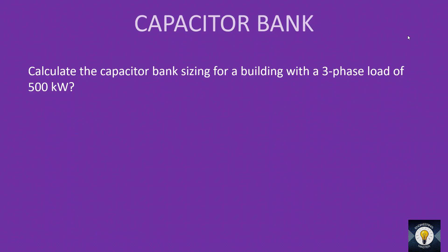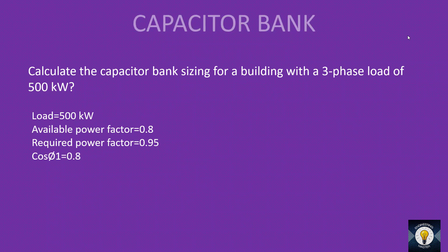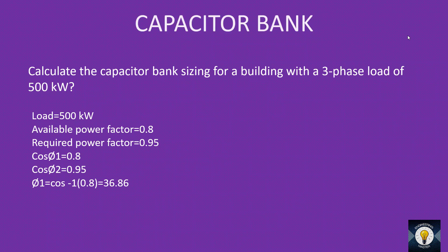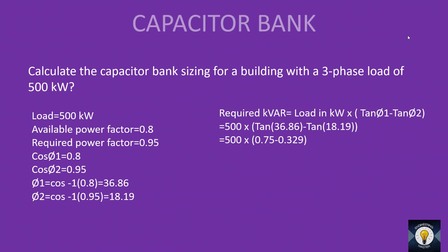Let us solve one more problem. Calculate the capacitor bank sizing for a building with a three-phase load of 500 kilowatt. Available power factor is 0.8, required power factor is 0.95. φ1 = cos⁻¹(0.8) = 36.86°, φ2 = cos⁻¹(0.95) = 18.19°. Required kVAR = 500 × (tan 36.86° − tan 18.19°) = 500 × (0.75 − 0.329) = 210.65 kVAR.